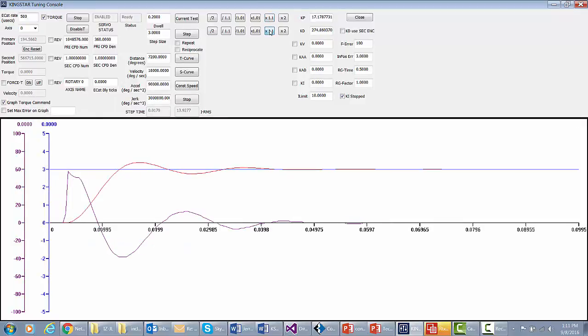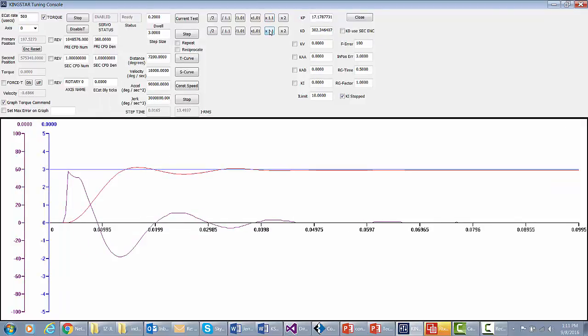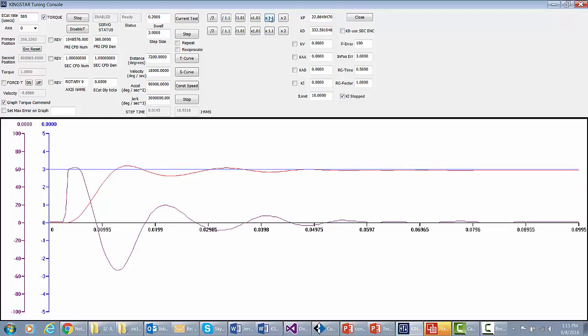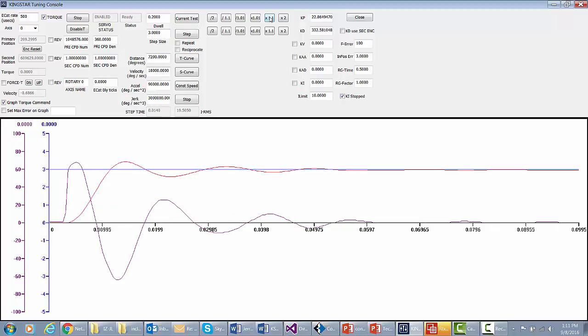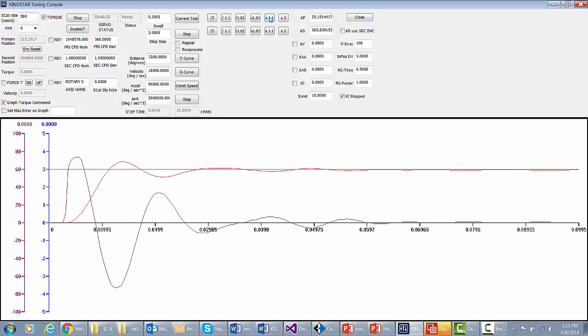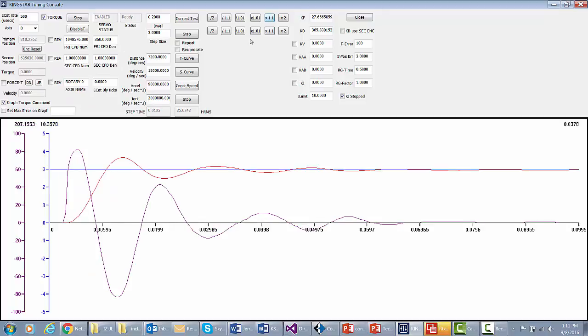And you can just work this in and continue back and forth. It's an iterative process, but you do know exactly which way to go. Right now, we're down to 14 milliseconds. I can add a little bit more on this. I'm down to 13.5. This is a good running servo at this point.